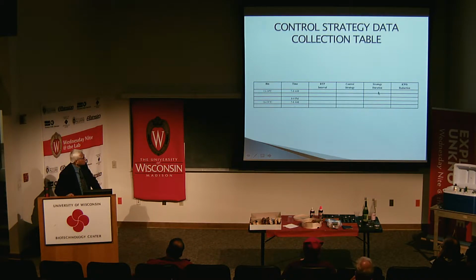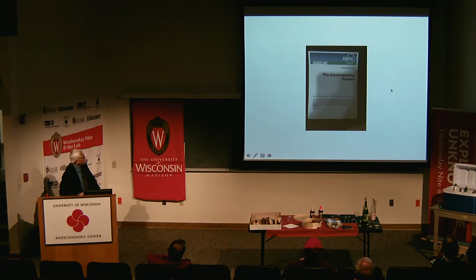And you calculate what is the strategy duration. You cannot leave it on forever. Many of the control strategies are interconnected, so they can last on some days for 15 minutes or half an hour, on some other days for 45 minutes, depending upon the control interactions. And so you also identify what is the kilowatt hour reduction. Now, the commissioning process I talked about, there are standards for this. This again is through ASHRAE.